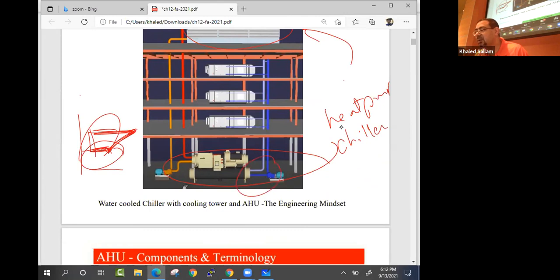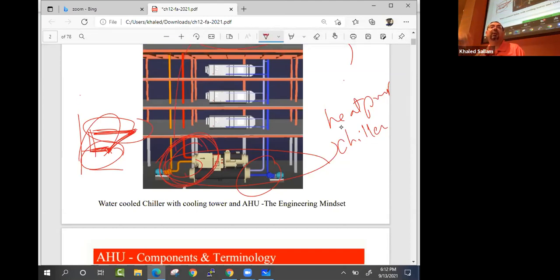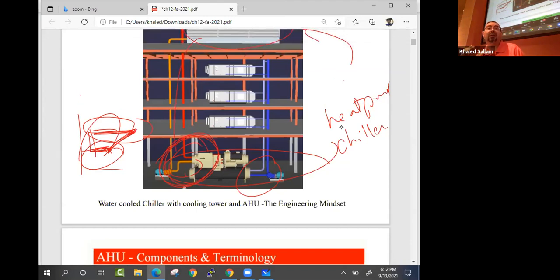That's the cold part, the cold water that's called chilled water. That chilled water goes and cools the building. The hot part, that's the condenser, is what's going outside to be thrown into the atmosphere in the cooling tower. So this gets thrown to the atmosphere, and this is the side absorbing the heat from the building.